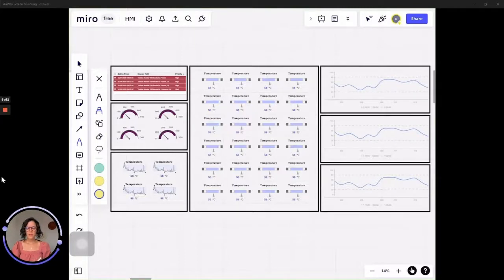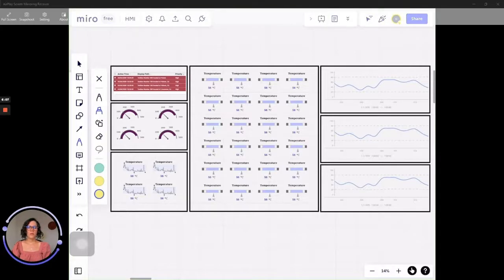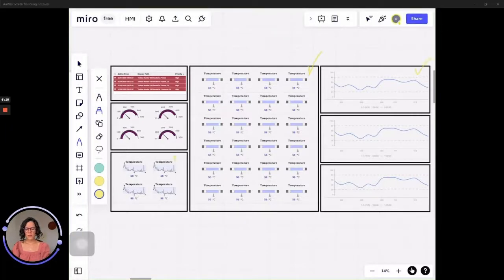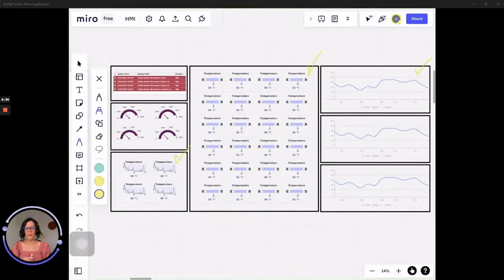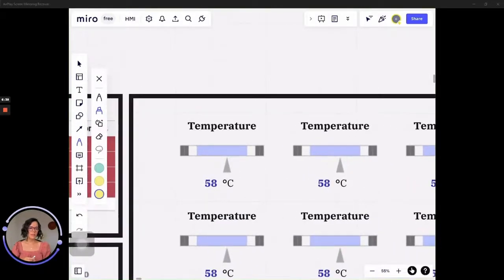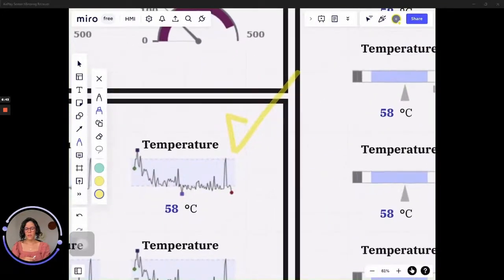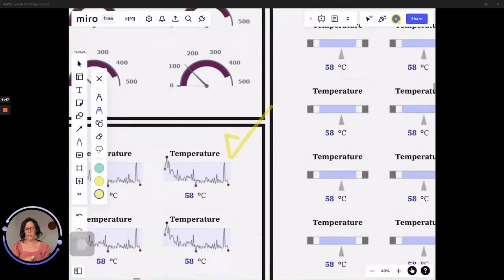The first thing I mentioned was: you have to think about what is the most important information to show in the overview. You can start by dividing your process into different areas — here I have different tiles, that means different areas. Find your process areas and decide what is the most important information for each area. Then use visual help to show the information — in this case, we are using analog indicators and sparklines to show the most recent historical information.